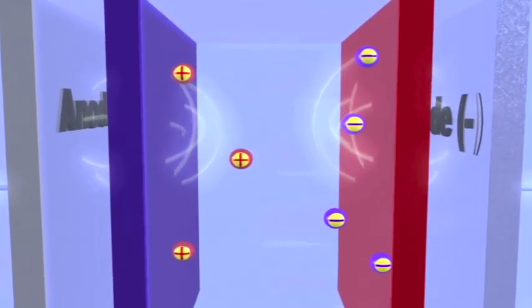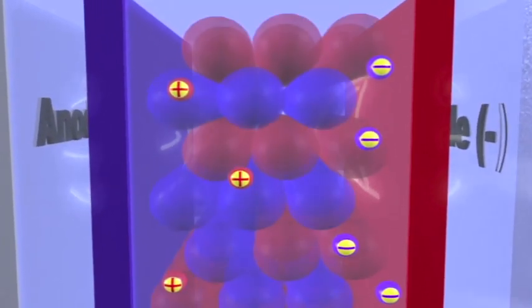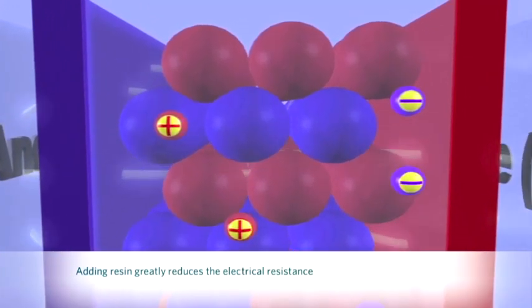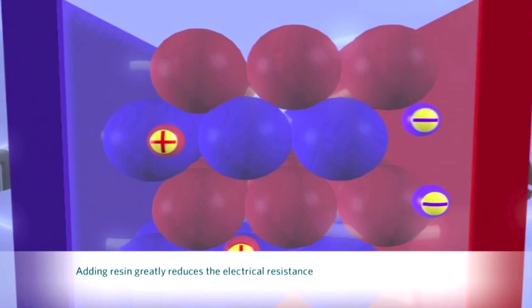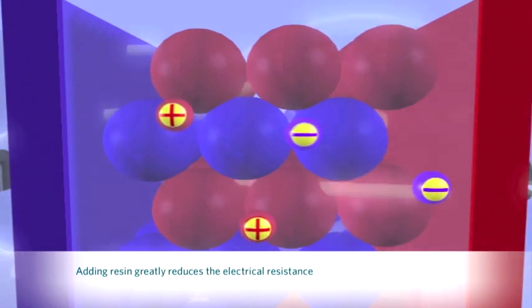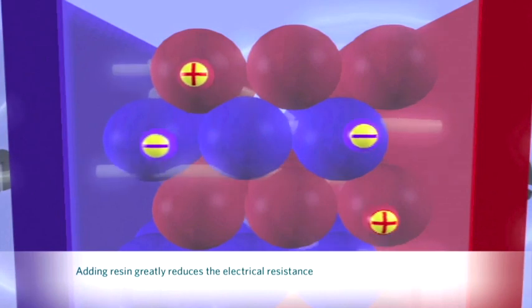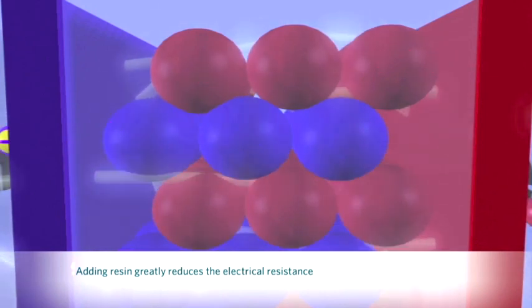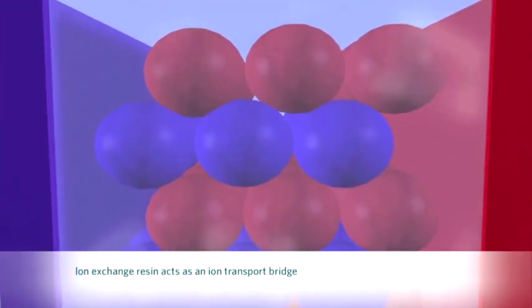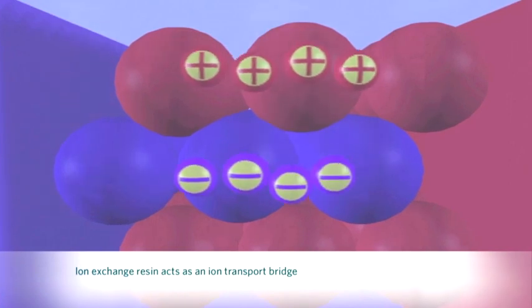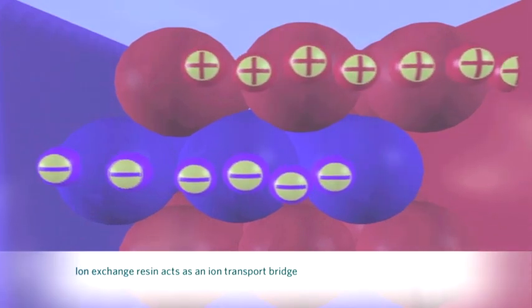IonPure CEDI technology solves this problem by sandwiching a mixture of cation and anion-selective resins between the two membranes. The large surface area now offered by the resin beads effectively eliminates the ion diffusion resistance and allows the ions to move freely, even in ultra-pure water solution. The surface of the resin beads acts as a conductive path, effectively acting as a bridge for the ions to move quicker toward the membrane surface, faster than if they were in water alone.